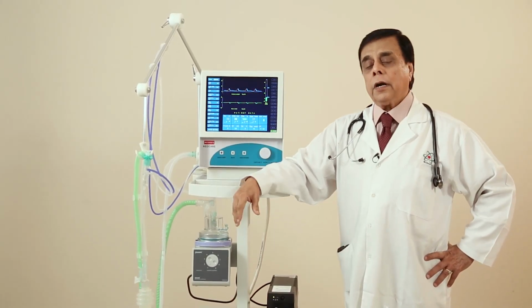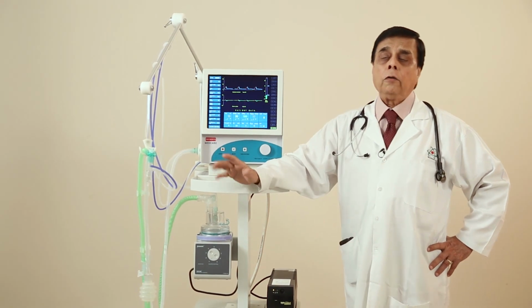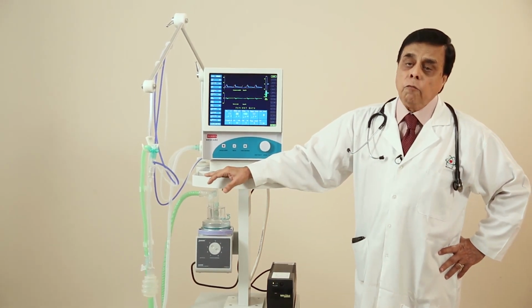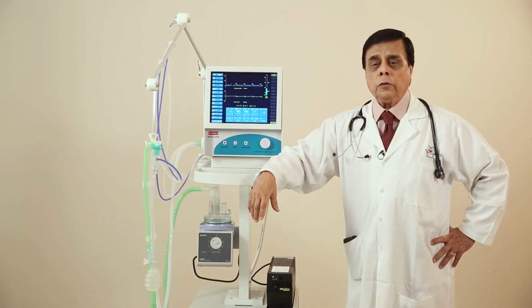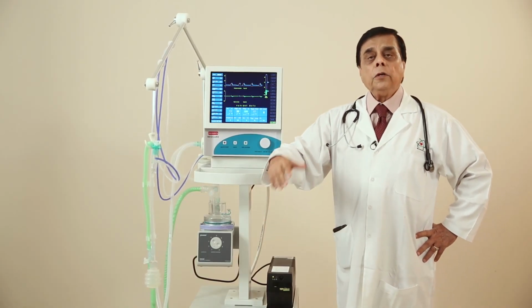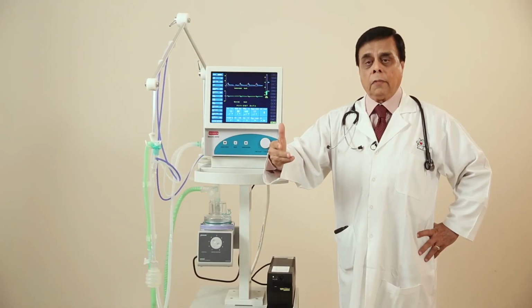Modes are, of course, SIMV, CPAP, spontaneous mode, assist control, and inverse ratio ventilation, which are all incorporated in this machine. And there is a pressure support and apnea backup also, which is very important, particularly when you are weaning the patient from the ventilation. Now there is an effective trigger system also in the ventilator, and we trigger the patient with a pressure and flow system, which makes the triggering so simple for them.